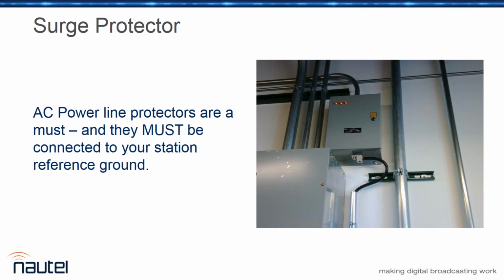So the big thing about surge protectors is location, location, location, just like real estate, just like transmitter facilities. You want to keep it as close as you can to the main electrical entrance, because the highest inductance, therefore the highest impedance to a lightning strike, will be the relatively small diameter wires to the surge box. So having your surge box way over by your reference ground isn't nearly as good as having it up by the AC lines, where the AC comes in.